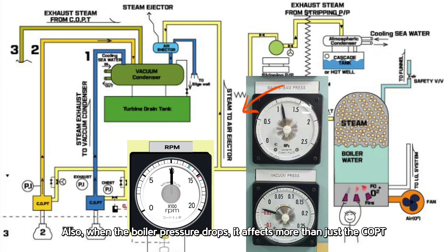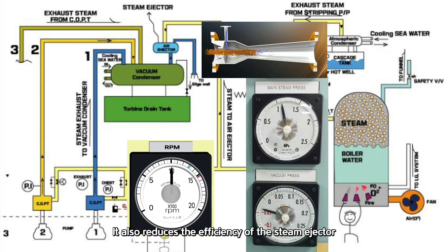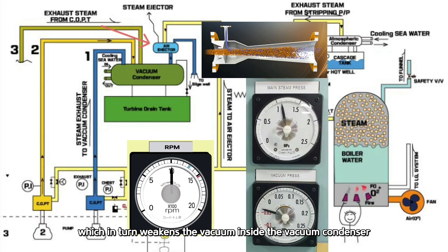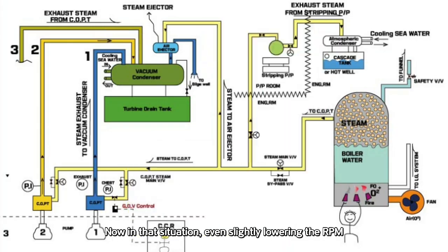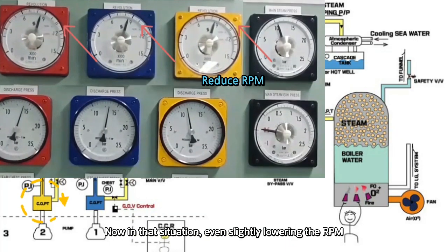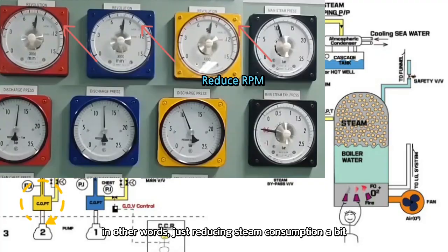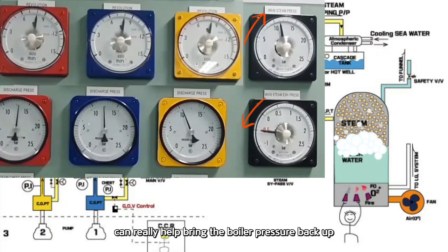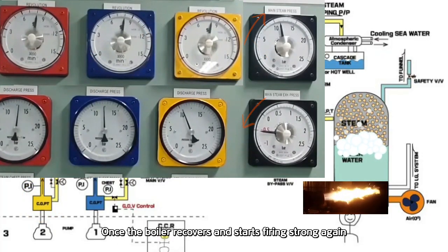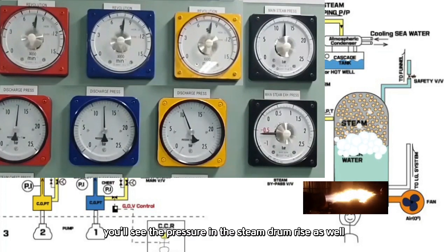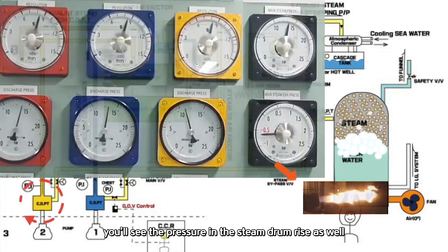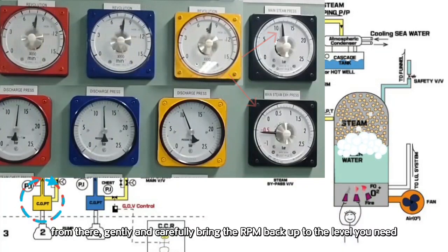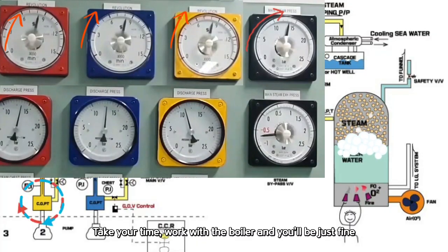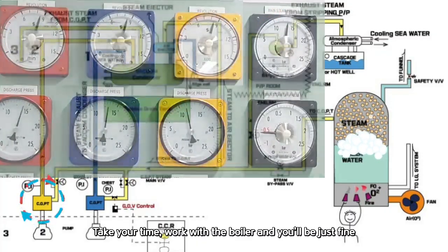Also, when the boiler pressure drops, it affects more than just the COPT. It also reduces the efficiency of the steam ejector, which in turn weakens the vacuum inside the vacuum condenser. Now in that situation, even slightly lowering the RPM, in other words, just reducing steam consumption a bit, can really help bring the boiler pressure back up. Once the boiler recovers and starts firing strong again, you'll see the pressure in the steam drum rise as well. That's your cue. From there, gently and carefully, bring the RPM back up to the level you need. Take your time, work with the boiler, and you'll be just fine.